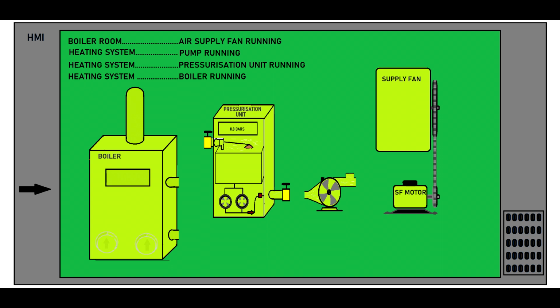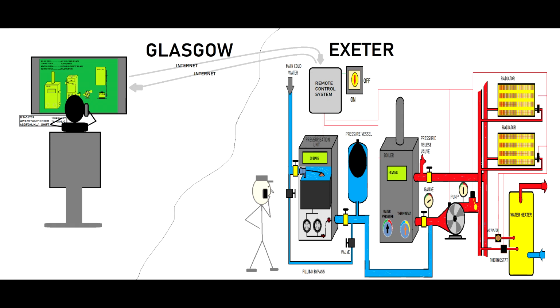In the next video, I will show you how I would integrate these. Again, the technician will turn up at the premises and say, well, you know, there's nothing wrong with the boiler. Unfortunately, I have a problem with the pressurization unit. I have a problem with the pump. I might have a problem with the ventilation system. And because they are supposed to be interlocked, the boiler doesn't run. But because the pump is not running, the boiler overheats itself.